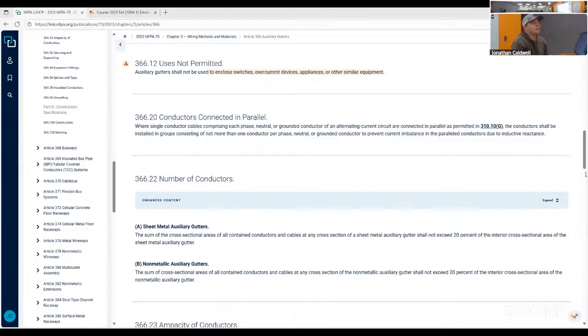I could say you could test this, but to test it in an actual way, you would intentionally have to mess up a service. So I don't recommend that. But you would see weird voltage ratings. Your power factor wouldn't be as good either. And you would also, if you had a harmonic, trying to remember what that device is called, in layman's terms it's called a power meter. It reads the power and all the harmonics on it and all that. But you would see a lot of harmonics come on two of those as well.